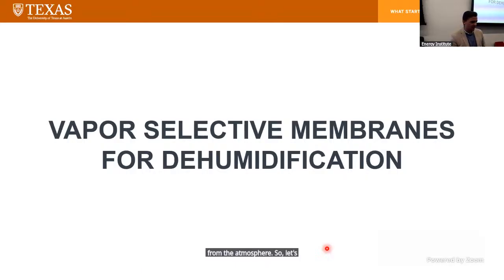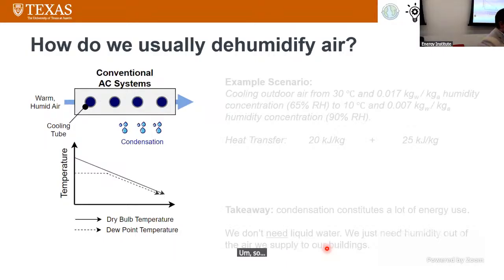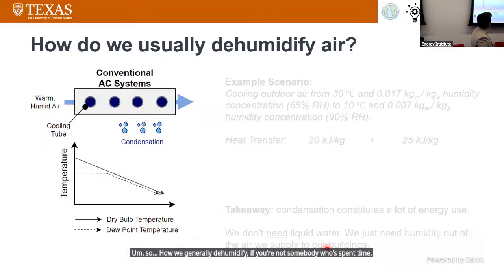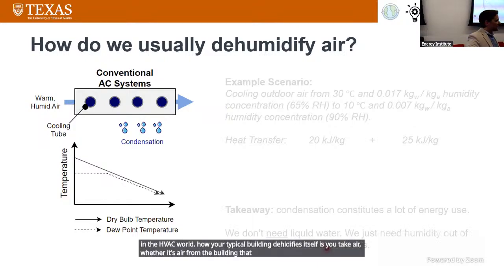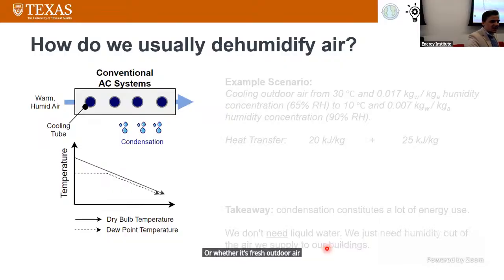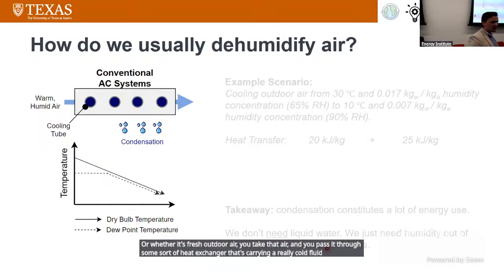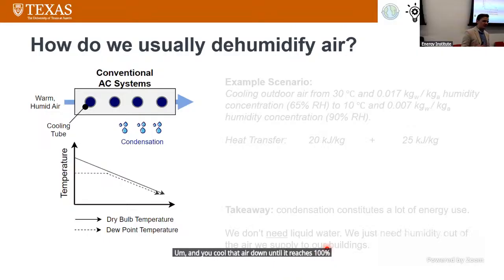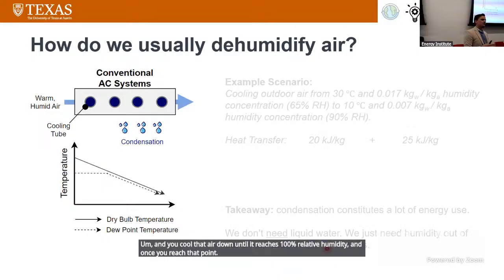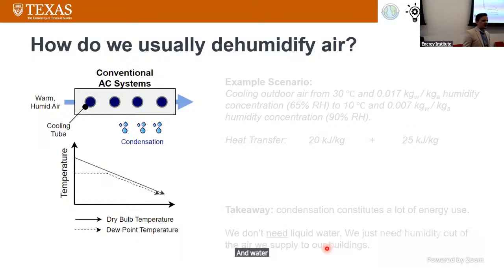Let's talk about dehumidification specifically. How a typical building dehumidifies itself: you take air - whether recirculated building air or fresh outdoor air - and pass it through a heat exchanger carrying a really cold fluid, like chilled water or refrigerant. You cool that air down until it reaches 100% relative humidity, and once you reach that point, you continue cooling the air down, and water has to then condense out of the air.